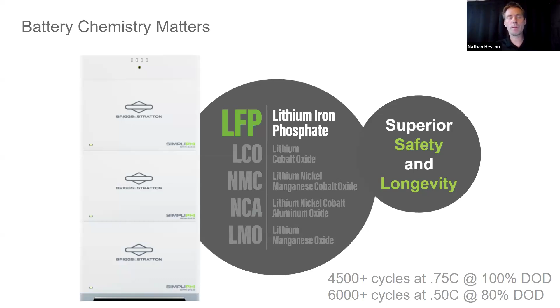A single stack of these batteries can discharge at 1C - that means that whole battery can discharge itself in an hour. Why would you want a high C rate? Maybe you have some big load that's going to come on, and you want to be able to power that load. We used the example of somebody wanting to know the overall maximum output of the inverter. If the batteries don't have enough output power to power that inverter, you'd need a very large battery bank to just maybe get your air conditioner running. So we want to make sure the battery stack has the power.